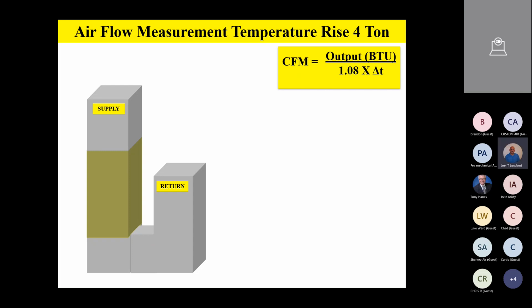All right, fellas, so we're going to do a temperature rise method one more time. This is a 4-ton unit, and we have the formula up there. In this second example, we have 241 volts. We actually measure 241 with the fan running and the heat strips cooking. And I clamp my amp clamp on there, and I see I've got 50.1 amps.